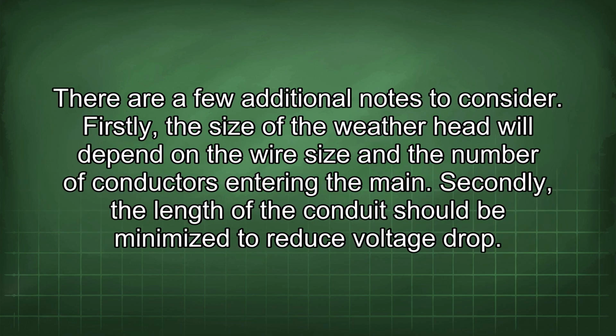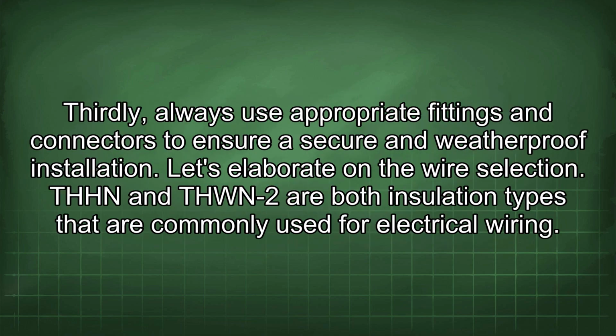There are a few additional notes to consider. Firstly, the size of the weatherhead will depend on the wire size and the number of conductors entering the main. Secondly, the length of the conduit should be minimized to reduce voltage drop. Thirdly, always use appropriate fittings and connectors to ensure a secure and weatherproof installation.